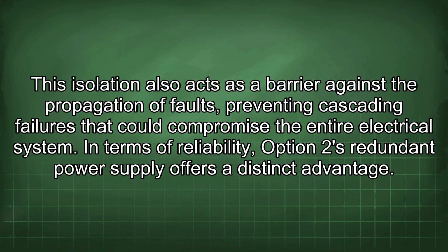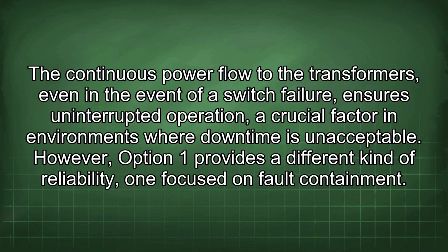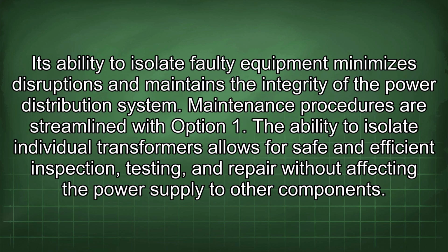In terms of reliability, Option 2's redundant power supply offers a distinct advantage. The continuous power flow to the transformers, even in the event of a switch failure, ensures uninterrupted operation, a crucial factor in environments where downtime is unacceptable. However, Option 1 provides a different kind of reliability, one focused on fault containment. Its ability to isolate faulty equipment minimizes disruptions and maintains the integrity of the power distribution system.